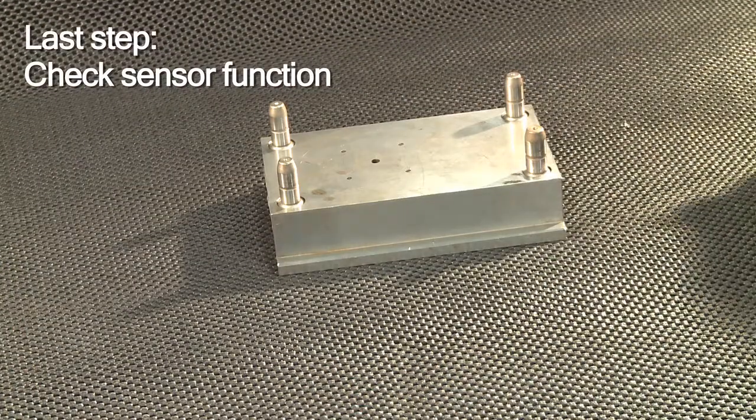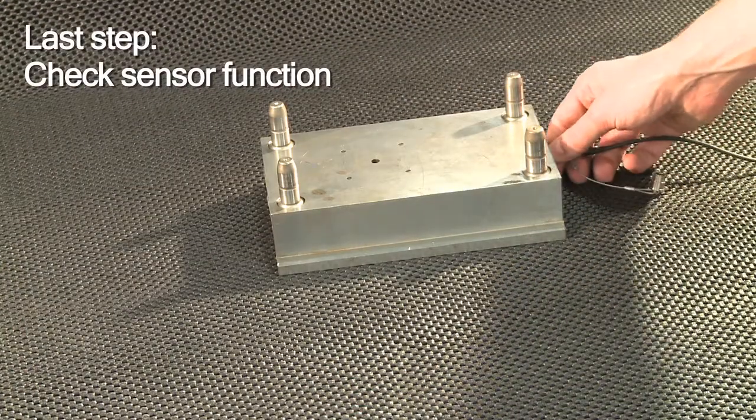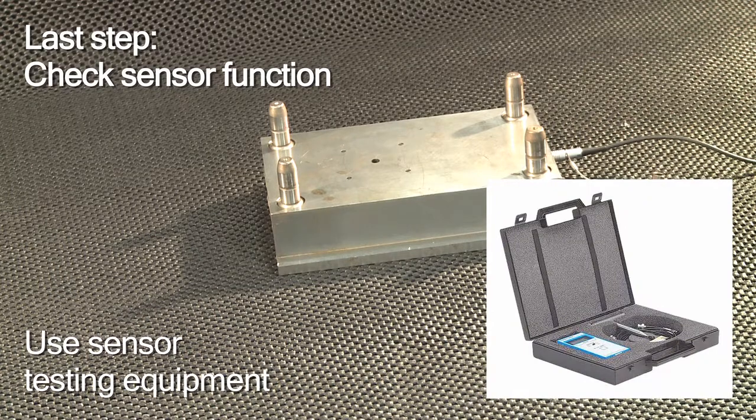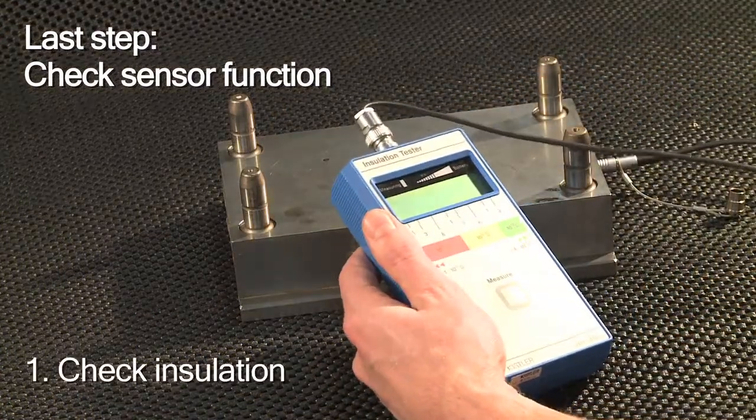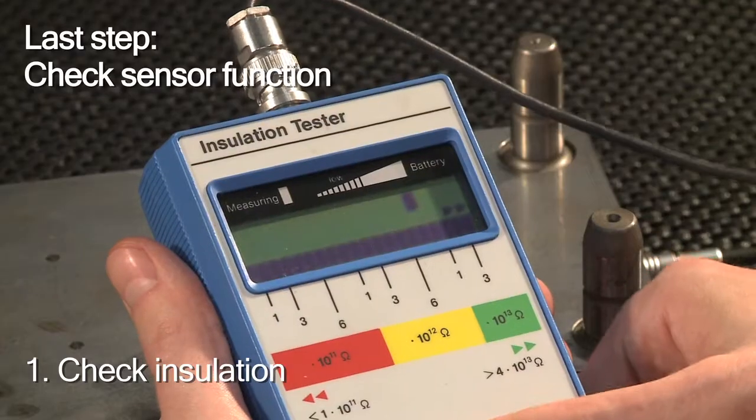To be sure that the installation was successful, you make use of Kistler's sensor testing equipment. First you check the insulation. The bar has to be well into the green field.